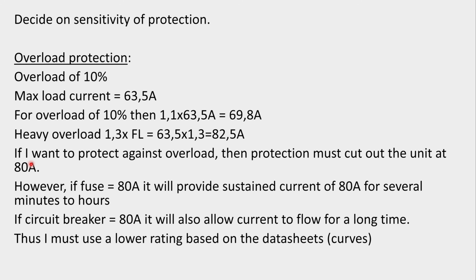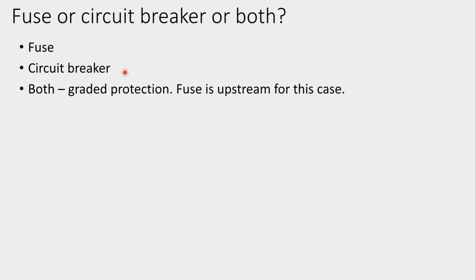So if I want to protect against overload, then the protection must cut out the unit at 80 amps. So you might think that let's put an 80 amp fuse in there, but an 80 amp fuse will not cut out the unit at 80 amps. In fact, if I put an 80 amp fuse there, the fuse will allow 80 amps for minutes, even up to an hour. While if I put a circuit breaker there of 80 amps, it'll also allow current to flow for a long time, and it might never ever trip. So I need to look at a lower rated protection device, and I need to base it on the data sheet. So the first question is, am I going to be using a fuse or a circuit breaker, or even both, in something called graded protection?